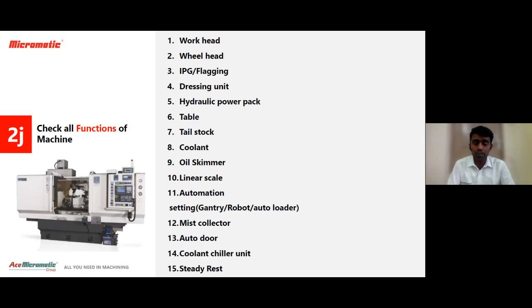And please remember, for linear scale, it should be dry air. It should not be lubricated air. It only should be dry air. And in case of automation, once again, the same repeated points are applicable. Move the gantry axis completely in MPG mode and cross-check for any abnormal load and noise. The same is applicable for robo and autoloader.